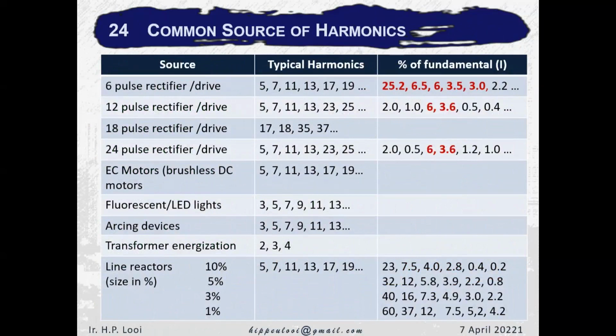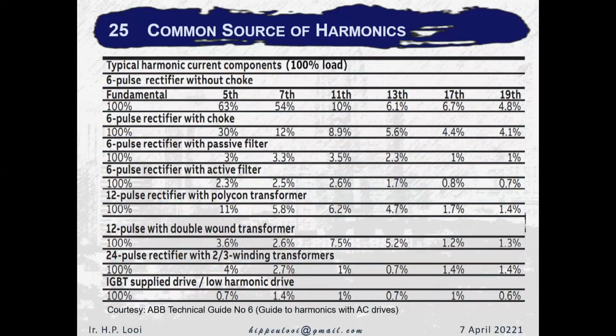Okay, these are some examples. You can see, okay, the next slide. The higher the pulse rate, the lower the harmonics. And you can also see, like a 6-pulse rectifier, if you add a choke, the choke actually acts as a filter, a harmonic filter. The fifth harmonic is actually reduced by half. Back to electrical theory, the number of pulses is how they shape the waveform. So fewer pulses means the waveform is less smooth, which means it will give more harmonics. So that's the fundamental theory.